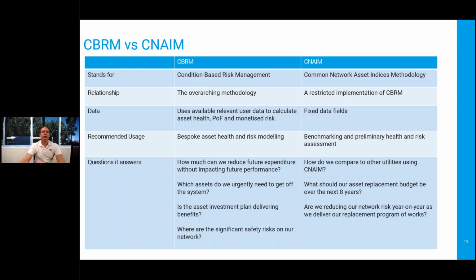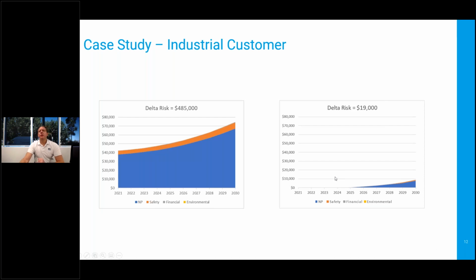Which then means, if we go back to that graph, you see it really scales down the delta risk in the current year to zero, and it's not until you get to 2026 that the health indices start popping up to the point where you're actually going to get some delta risk. So that's how the risk modeling was done for that customer to understand the cost benefit of doing those cable remediations.